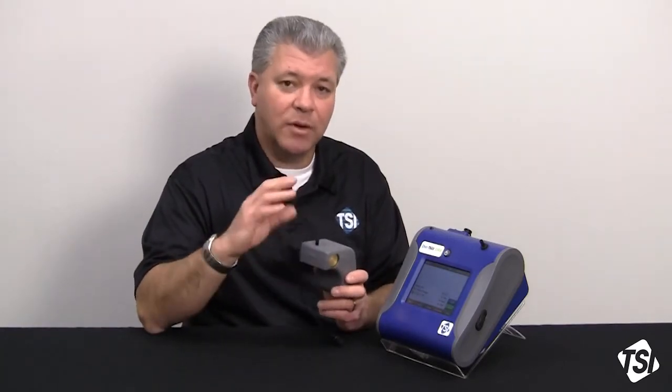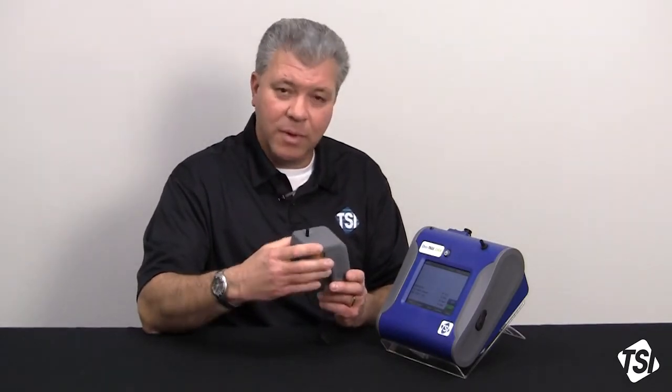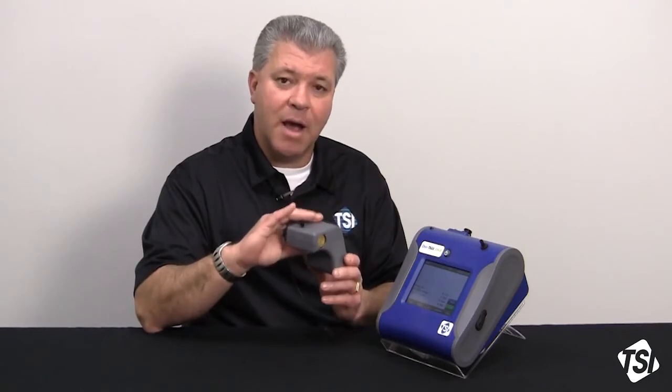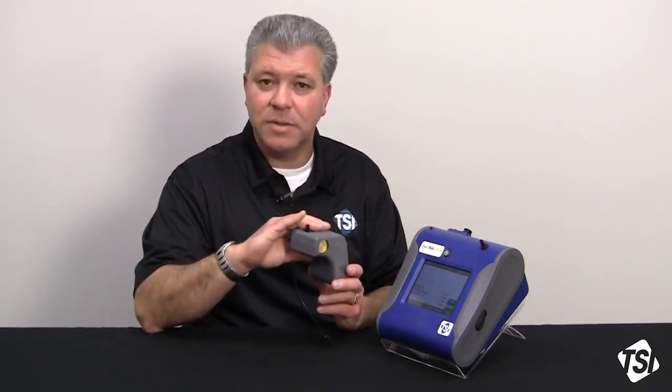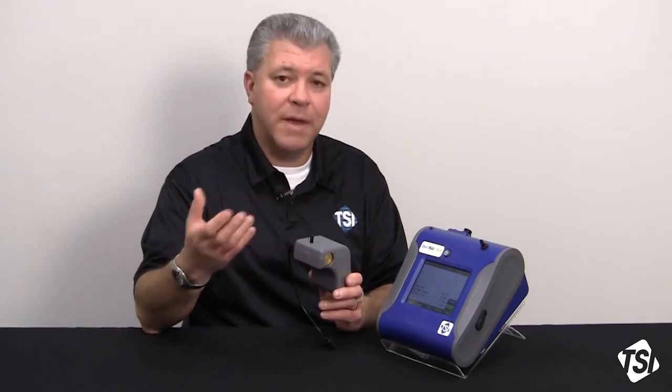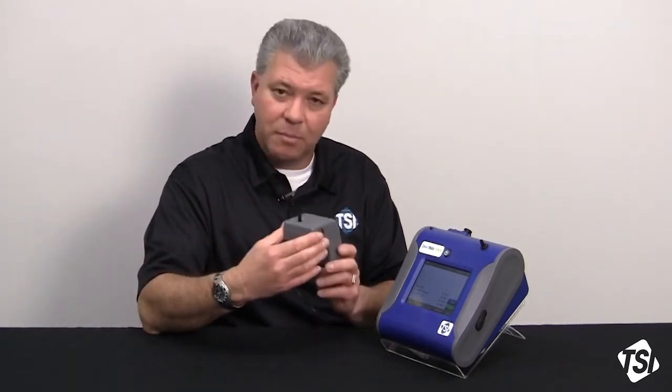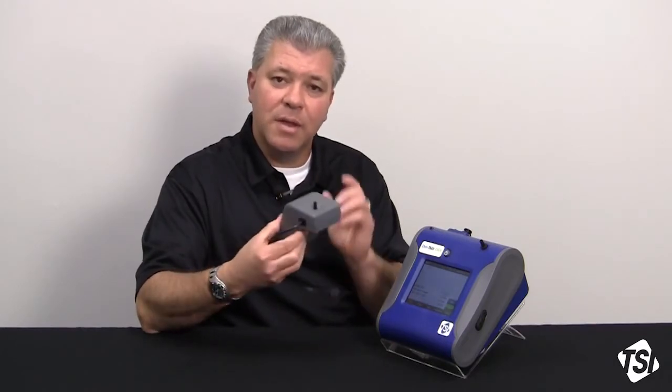Now, there's a couple of things with the Auto Zero module to note. The most important thing is that your logging interval can be affected. With the use of the Auto Zero module, you can't go any shorter than a 2-minute logging interval. The reason is, once you start, an Auto Zero will take 60 seconds. If you're doing that at less than a 2-minute log interval, you may affect more than one data point. We're trying to affect the least amount of data points possible. By doing that, 2 minutes will certainly ensure that only one 2-minute data point will be lost.